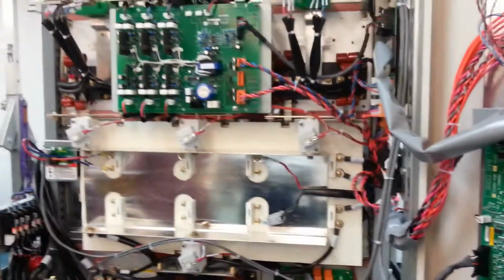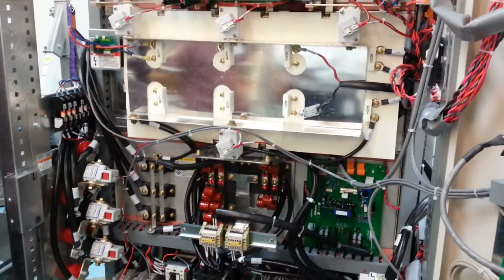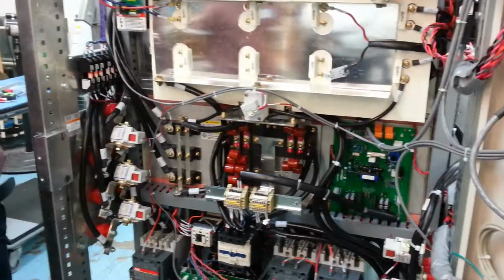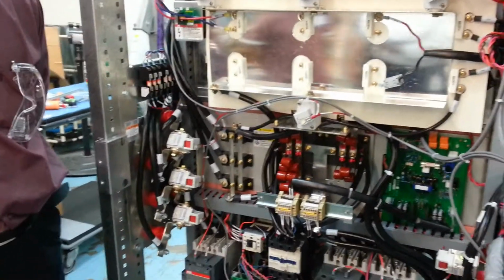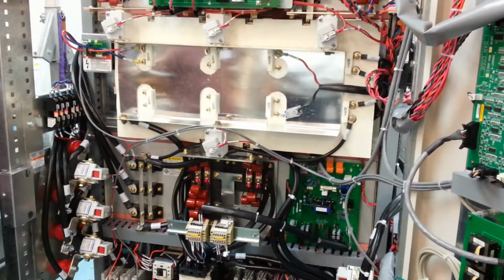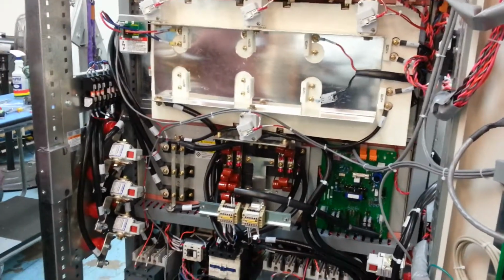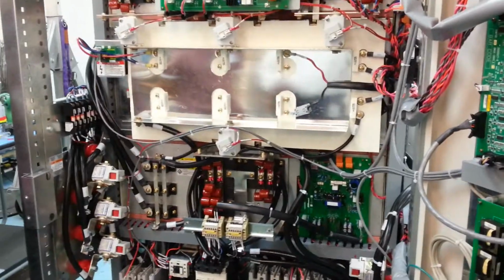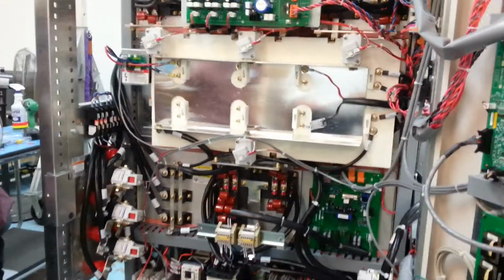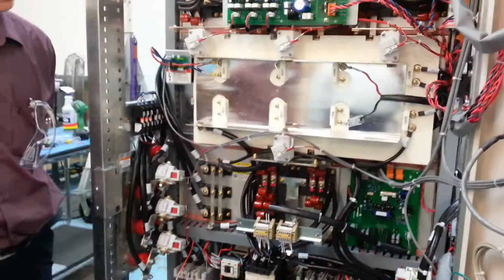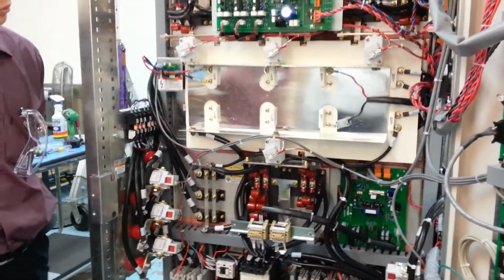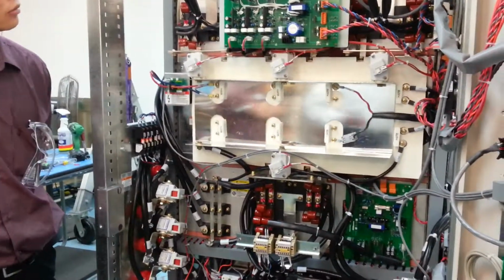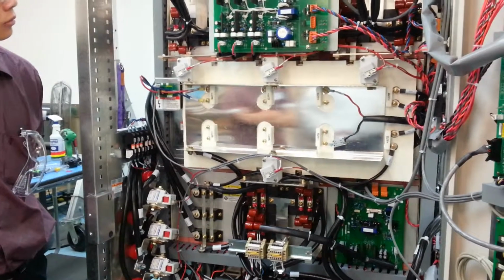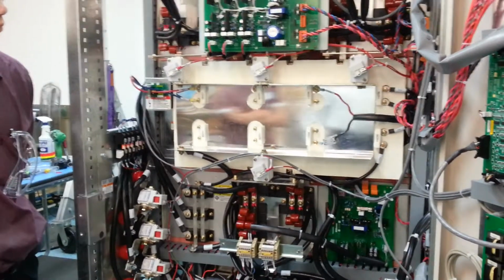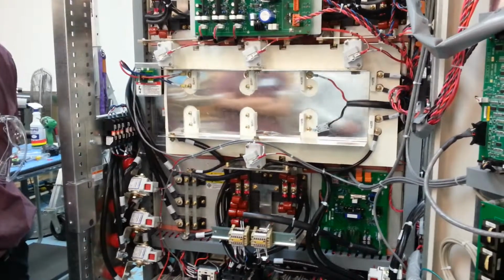Most of the time UPSs stay in a controlled environment, which is normally anything under 40 degrees C. So 104 degrees Fahrenheit. Most of the time a UPS won't go out of an environment more than 70, 80 degrees because it's usually in a building inside, a controlled environment somewhere. And then the customer will normally have an evacuation for the, in this case, several thousand BTUs, which is also at the top. Most UPSs are in the mid 90 percent efficiency range. That still means 5% losses over 180 days. So that's quite a few BTUs to get rid of. Yeah. So.